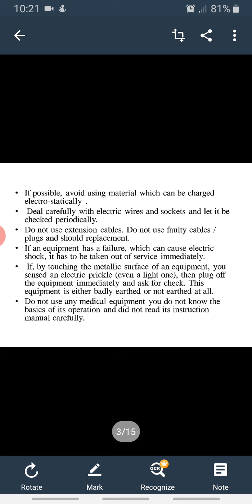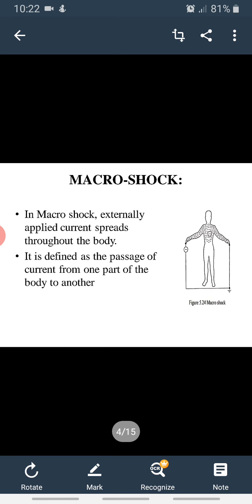Do not use extension cables, do not use faulty cables and plugs. If an equipment has a failure which can cause electric shock, it has to be taken for service immediately. If we are touching any metallic surface of an equipment and we sense electric shock, then plug off the equipment immediately and ask for a check, because this equipment is either badly earthed or not earthed at all. Do not use any medical equipment if you do not know the basics of its operation and have not read its instruction manual carefully. Next one, macro shock.